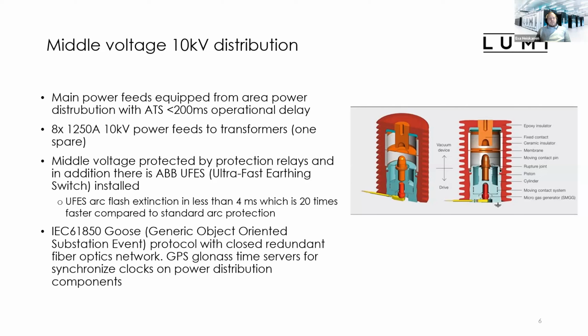Our medium voltage is protected by protection relays, and in addition there is an ABB ultra fast earthing switch installed. This ultra-fast earthing switch is an effective combination of specific arc detection relays and associated arc quenching devices consisting of a so-called primary switching element. And in case of arc flash, it is extinguished in less than 4 milliseconds, which is 20 times faster compared to standard arc protection. And as you may have seen what arc flashes can cause for the power distribution, this eliminates most of the damage if that kind of event occurs in the power distribution.